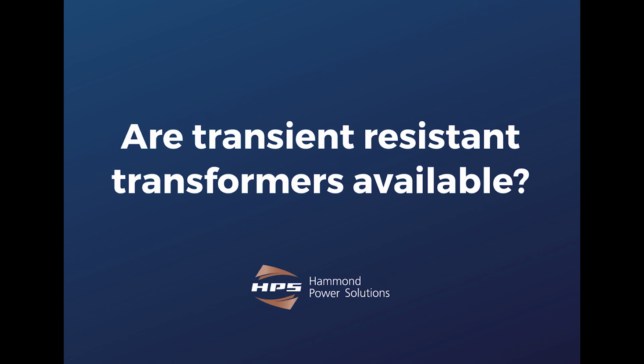First of all, part of that might be the BIL, basic impulse level. As we said, for dry type, we can go up to 250 kV BIL, which means we can handle a 250,000 volt spike and shouldn't arc. Liquid filled, obviously, especially in high voltage applications, can go much higher than that. So that is one method. What is the BIL rating for the transformer, and what is the expected maximum voltage of your transient?